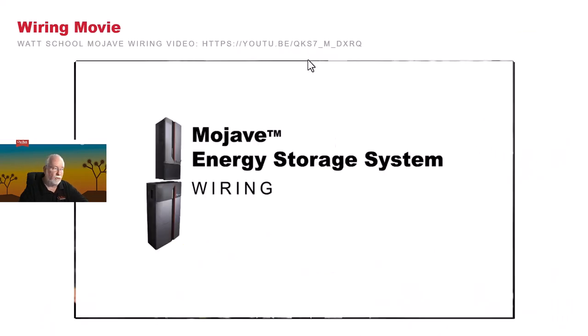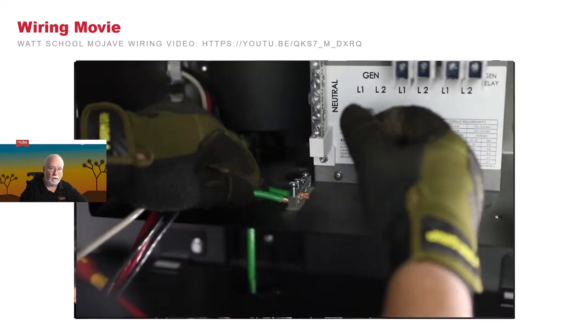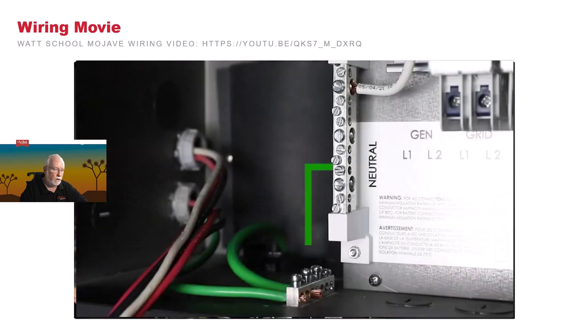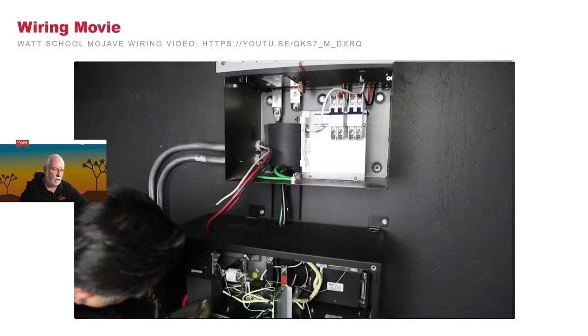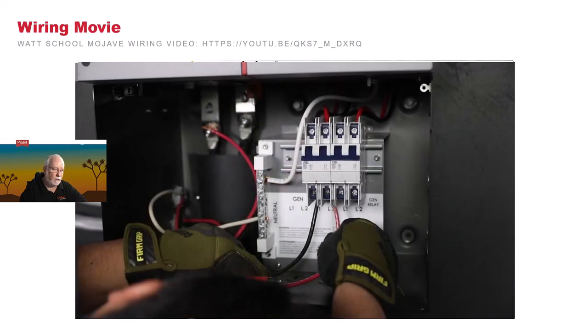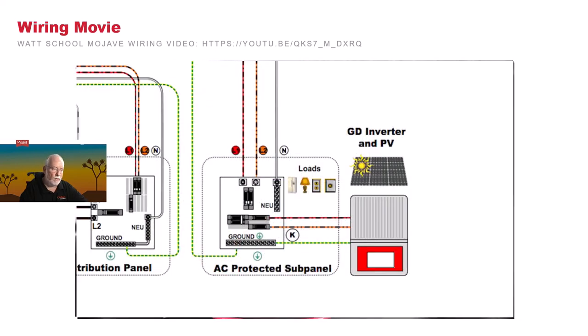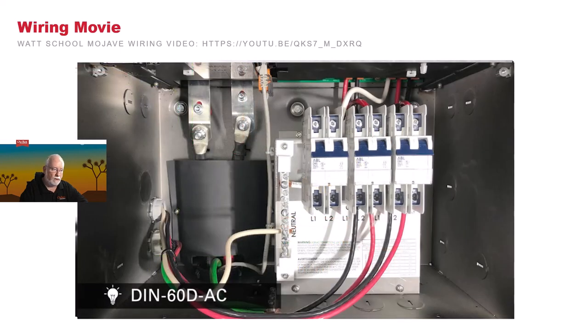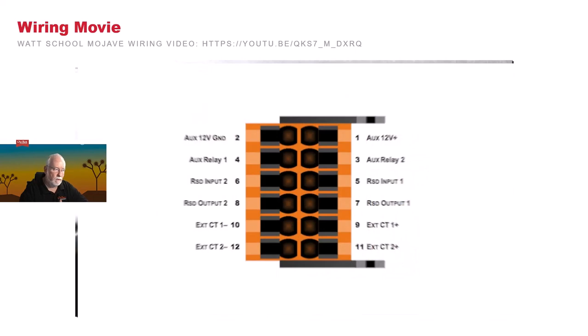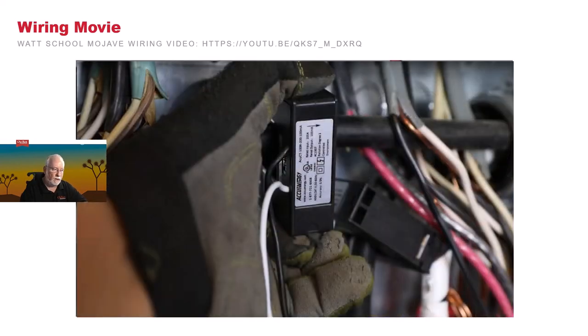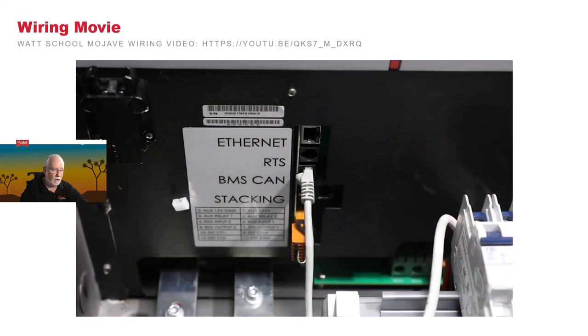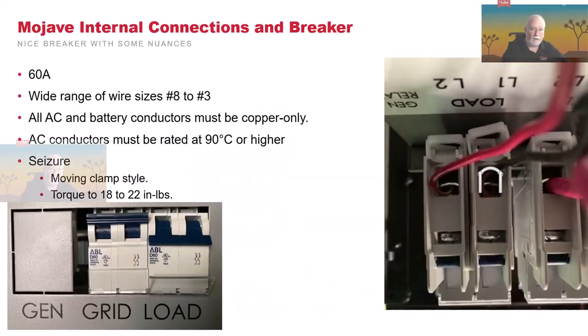There's also a really good video, again, another Mojave video. This will walk you through each one of the things of wiring it. So Jorge will show you the ground side. Effectively, he'll talk about the neutral ground bond, then he'll talk about the battery wiring, bringing in the line 1, bringing in the loads on line 1 and 2, then the addition of a generator. He'll talk about the multi-use connector and the connection of the CTs. Now, if you notice on the CTs, there's an arrow, that's current direction, and then there's also a label on it. Follow the directions on how to insert these. He'll show the low voltage connections like the CAN bus.